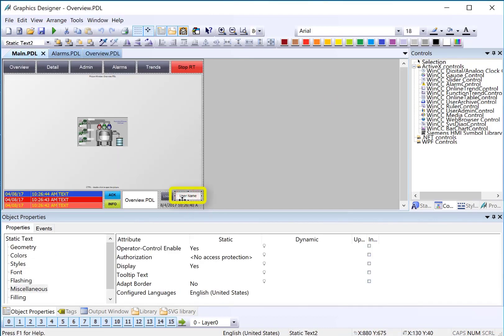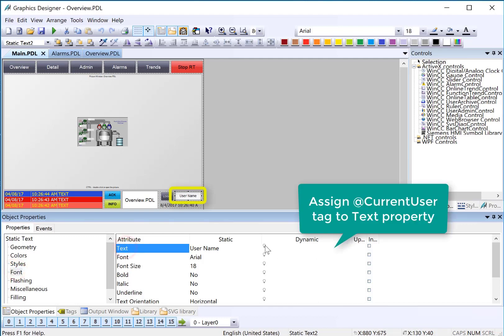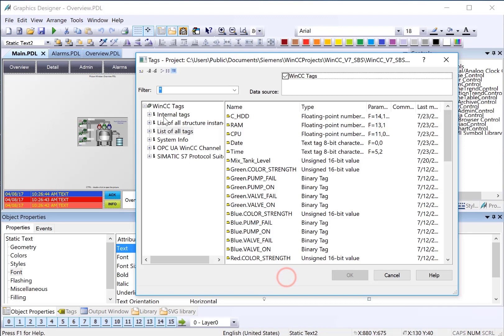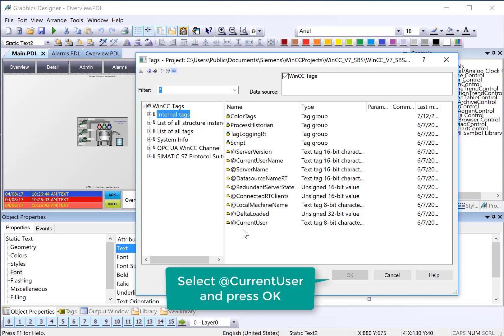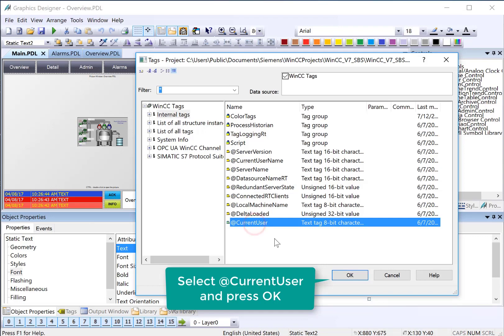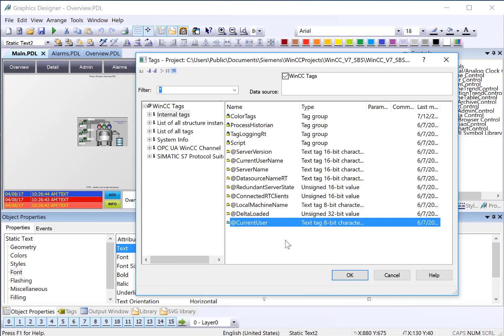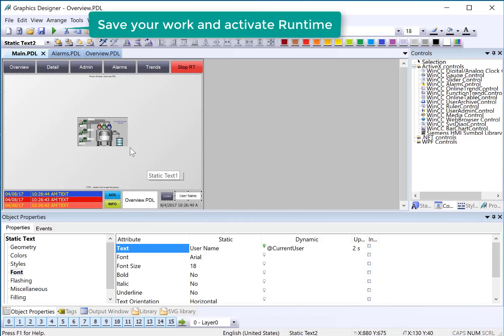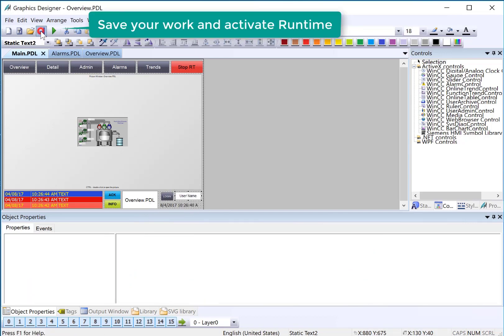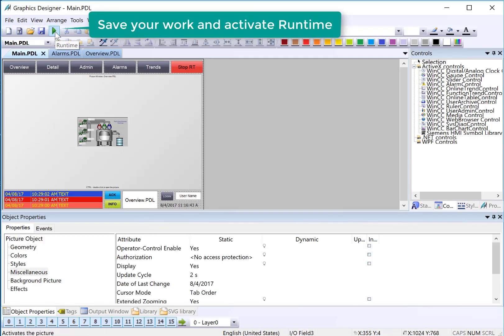Back on main PDL we need to set up to show the user name who's logged on. We're going to select our text box and on the text property we're going to right click and do tag. Under internal we have system tags that are denoted with an at sign. These are tags created by WinCC for your use and we are just going to choose @CurrentUser and click OK. That way any logged on user's name will show in this box and we'll click Save.